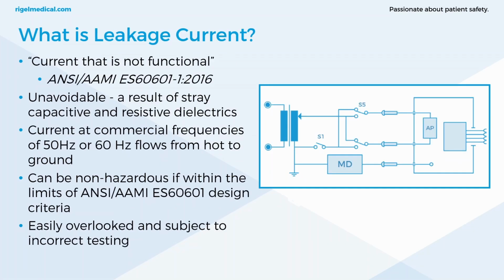Now what is leakage current? It's any current that is non-functional according to 60601. It's unavoidable, and it's easily overlooked and subject to incorrect testing. So all mains powered equipment is developed to only ensure safe levels of leakage current are achieved, not completely eliminated. You can never completely get rid of leakage current. It's always going to occur due to capacitive coupling.